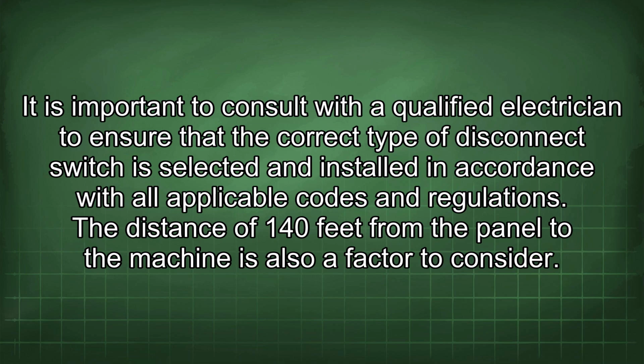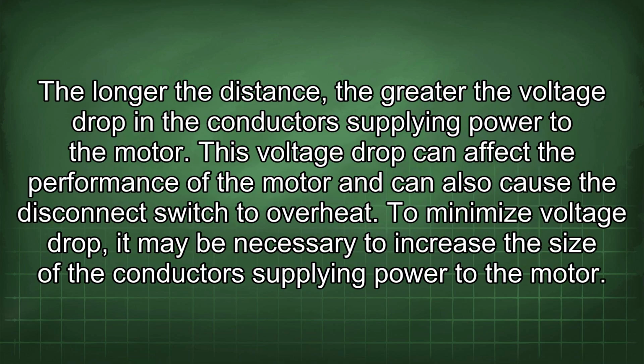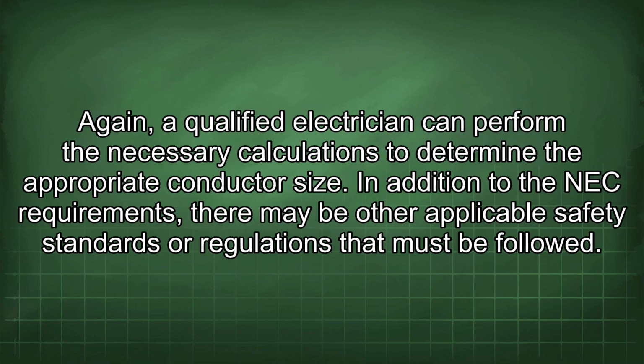The distance of 140 feet from the panel to the machine is also a factor to consider. The longer the distance, the greater the voltage drop in the conductors supplying power to the motor. This voltage drop can affect the performance of the motor and can also cause the disconnect switch to overheat. To minimize voltage drop, it may be necessary to increase the size of the conductors supplying power to the motor. Again, a qualified electrician can perform the necessary calculations to determine the appropriate conductor size.